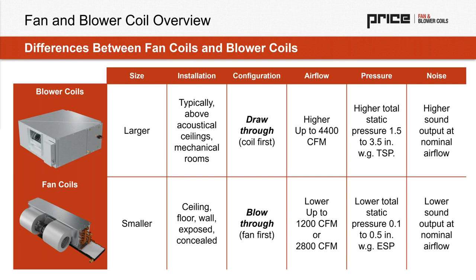Where they're installed is also a considerable difference between the two. So a blower coil, by the nature of its size, its configuration, and also the sound it generates, is often above acoustical ceilings or in mechanical rooms, where a fan coil can actually be mounted exposed directly in the space. We can break those paradigms, and we'll talk about how and why you might choose to do that and how you can address acoustical concerns. But those are some of the major differences.